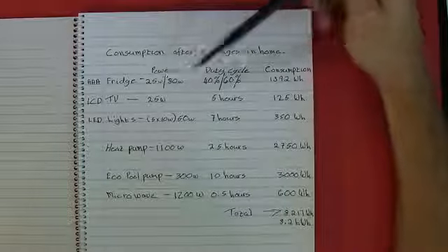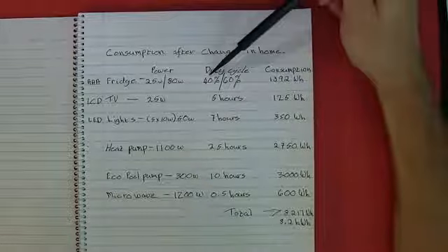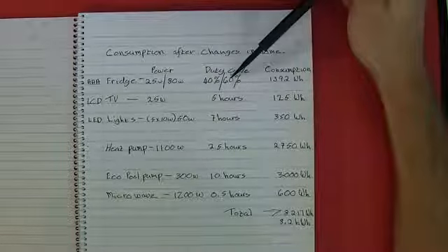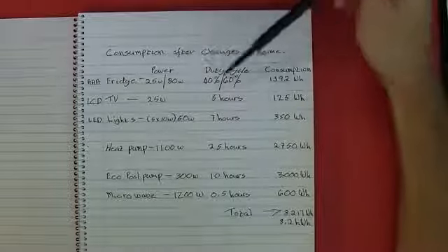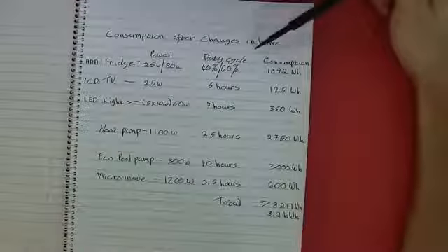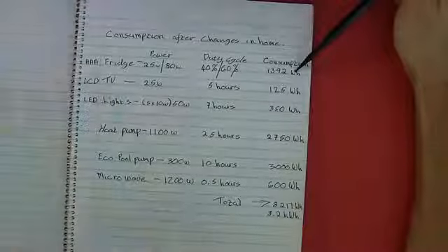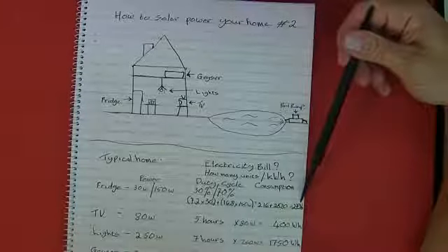The cold air doesn't escape. So it might spend more time in the low power state, like 40% versus the 30% previously, and only 60% of the day in the higher power mode, which is already less. So based on that, without going into detail on the calculations, that would come down to 1,392 watt hours versus previously 2,736.